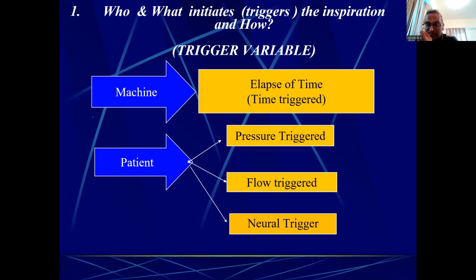So basically when the patient breathes in the first microseconds, because we breathe at 20 per minute, that means our cycle time is 3 seconds. Our inspiratory time is 1 second. If the machine takes 0.5 or 0.6 seconds to know that I'm beginning to breathe, there is no use if it gives me a breath at the very end of my effort, right? But the modern ventilators do it in microseconds.